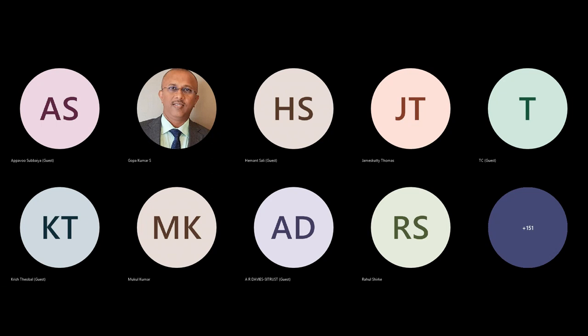Because we already have crores of UPS in the field, it is highly impractical to make people change all the UPS or configurations. In my opinion, with available UPS and connections, outgoing of UPS with the incoming neutral of transit or EB supply, there should be some practice. We should come out with a white paper on this. I can send a paper to the CEA, requesting them to go through and make a white paper, whether through the local EB authorities, the inspectorate, or the CEA, whatever may be. That can serve the people.